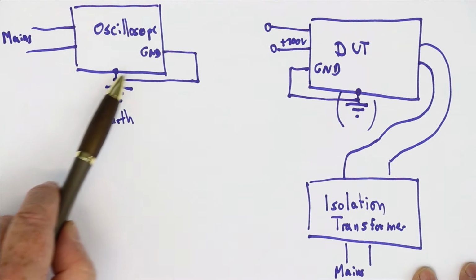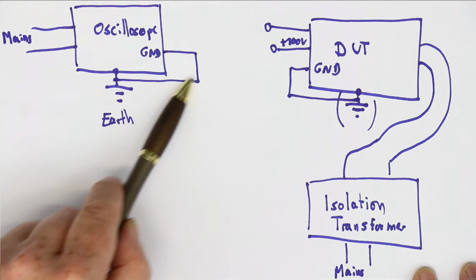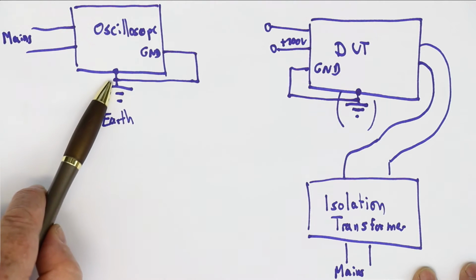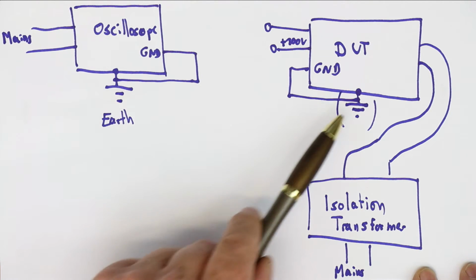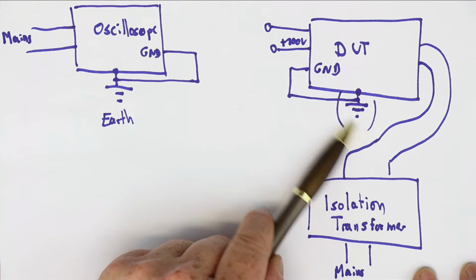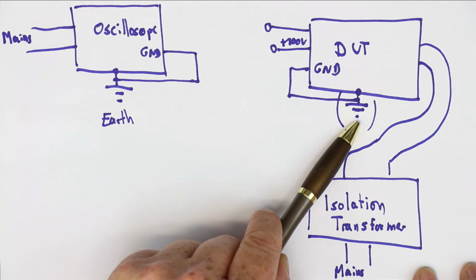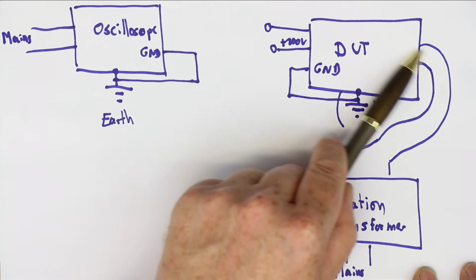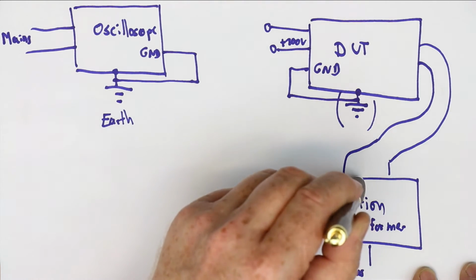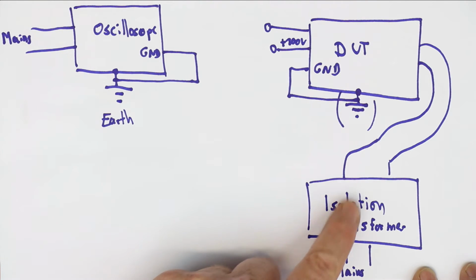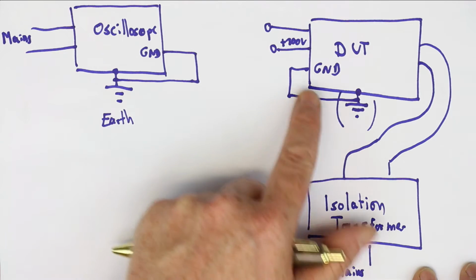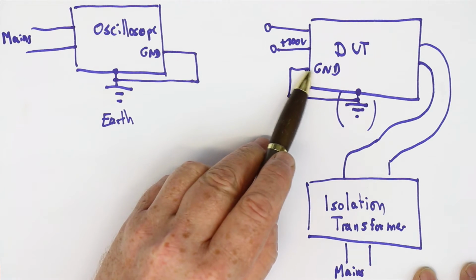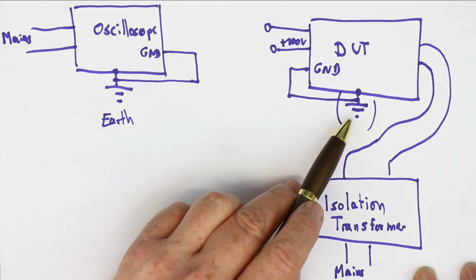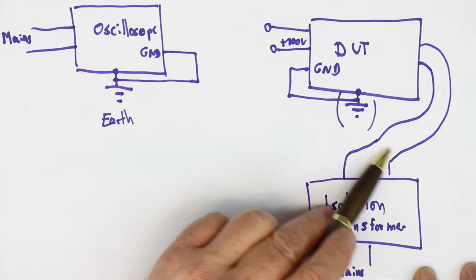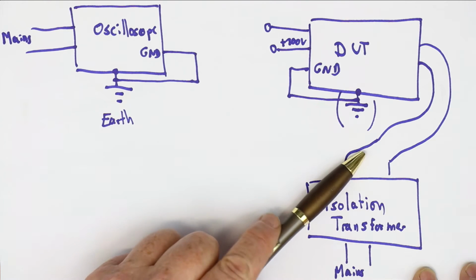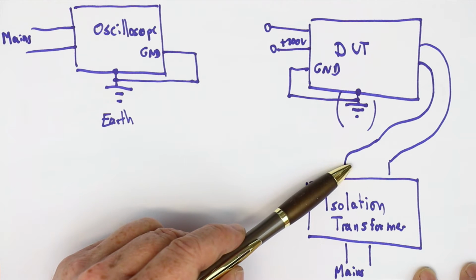There's no change in the connection of your oscilloscope - it's still connected to Earth, and thereby the ground of your oscilloscope is also connected to Earth. But we have interrupted the Earth connection from the device under test, because we plug the mains power plug directly into the isolation transformer. Thereby the case and ground are not connected to Earth, since we don't plug the power plug directly into the wall outlet, but put the isolation transformer in between.